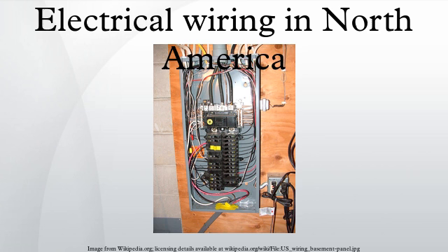The neutral is connected to the center tap of the power company transformer of a split-phase system, or the center of the Y connection of a polyphase power system. The United States electrical codes require that the neutral be connected to earth at the service panel only and at no other point within the building wiring system. Formally, the neutral is called the "grounded conductor".